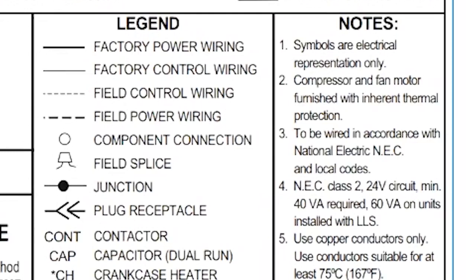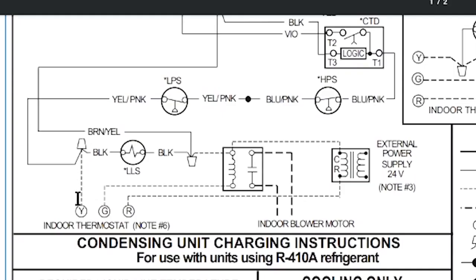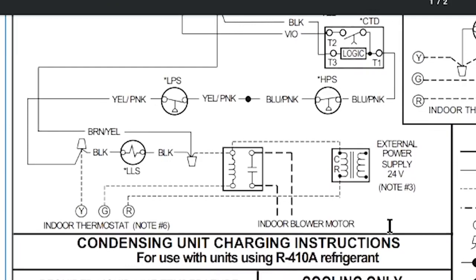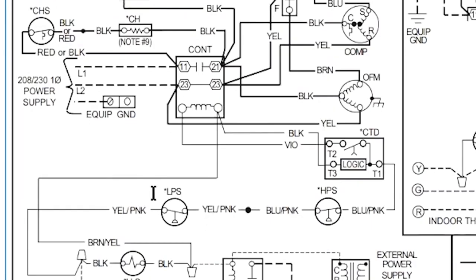A component connection field splice is something you make in the field with a wire nut — you can see the Y wire coming up and connecting to a wire nut. If you have to use an external power supply, you'd connect that yourself. Reading the notes and legend first can really help. Also pay attention to little stars, because that means there's something more to look at.